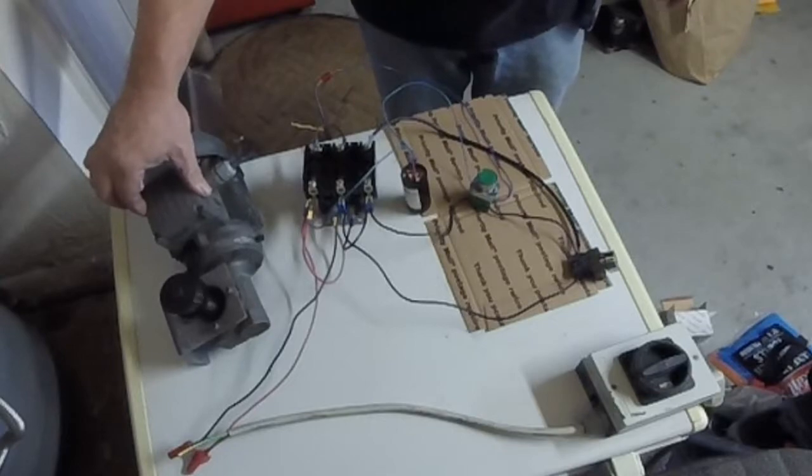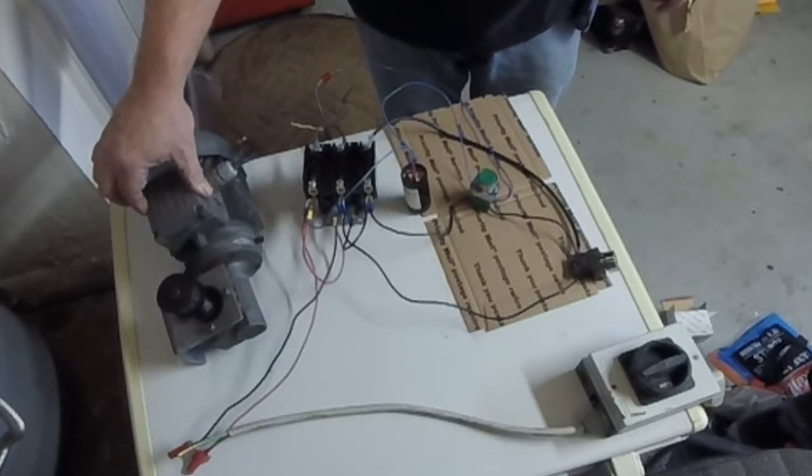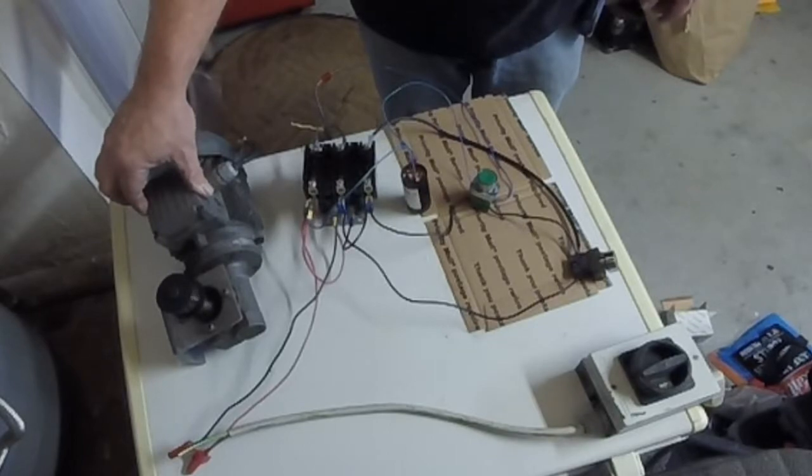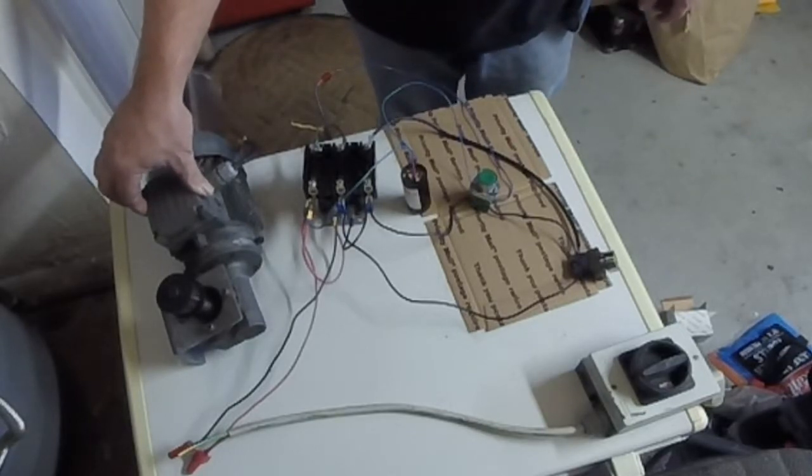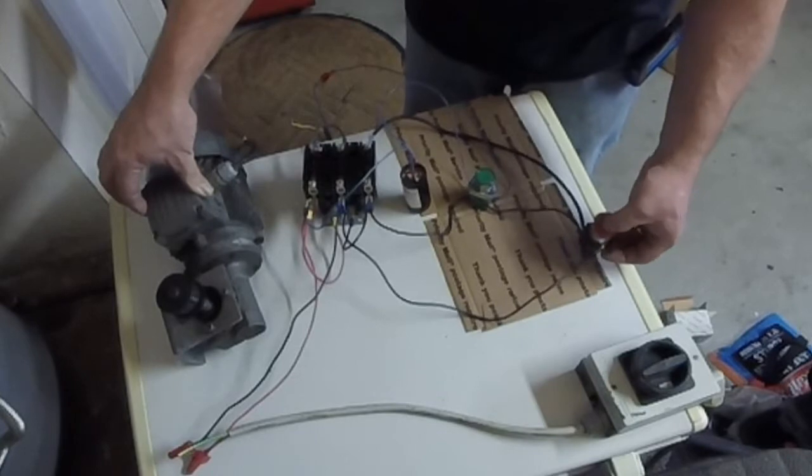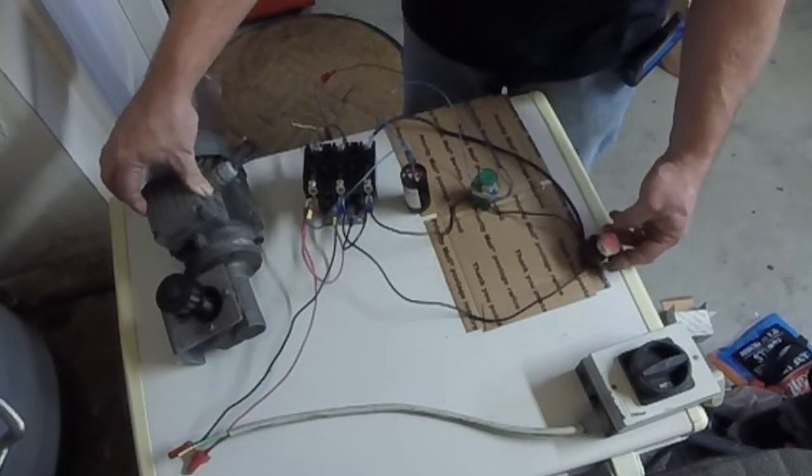And it does. The motor sounds like crap because it's really old and the bearings are bad. But believe it, it's running on single phase power right now. Contactor's pulled in and it's running on its own. Anytime you want to stop it, you hit the red button and it stops.